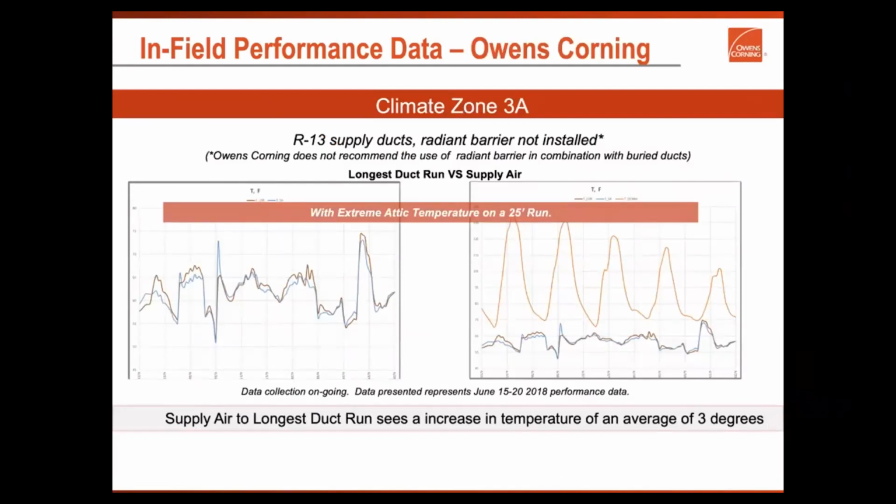Okay, cool. And mind you, it takes a long time to find where the unit is running constantly, because remember how I said that I argued with the installer, saying, hey, look, we need a 2.5 ton. He's like, no, I'm going to put a 3 ton. I don't trust you. Well, this is what you get. You get short cycling. So finding a time where the system is running at a continuous cycle to where you can measure both supply and return, that's what we're looking at.